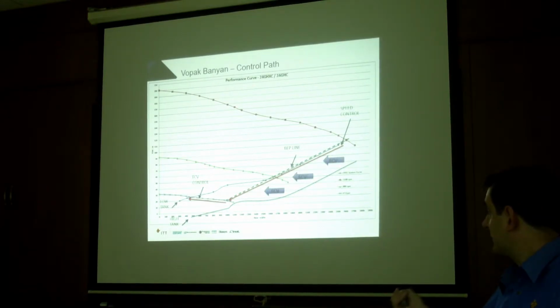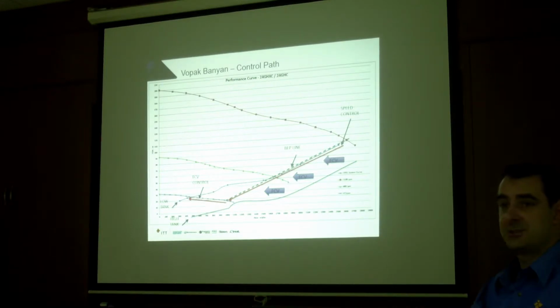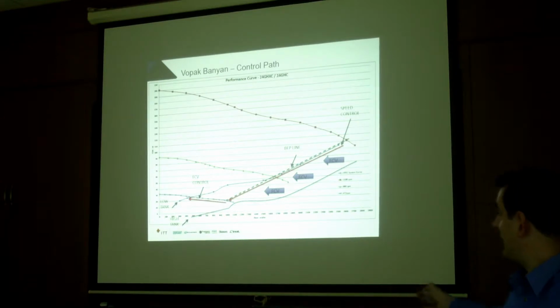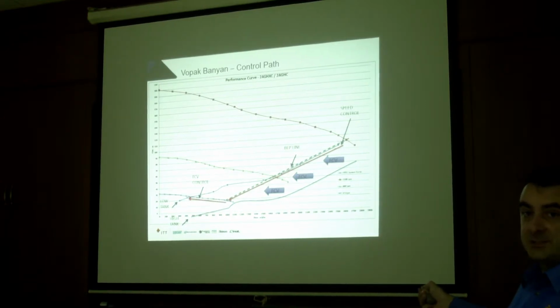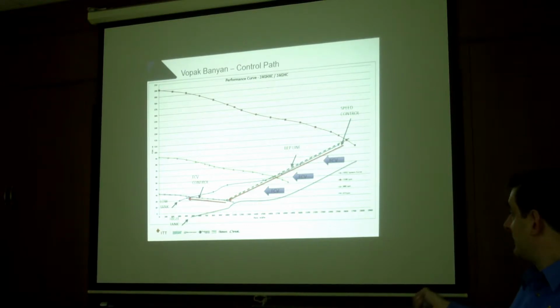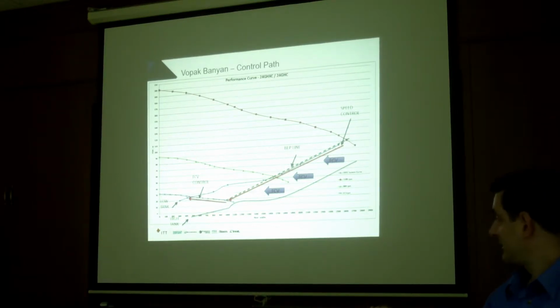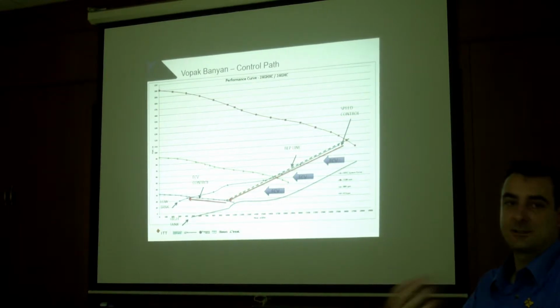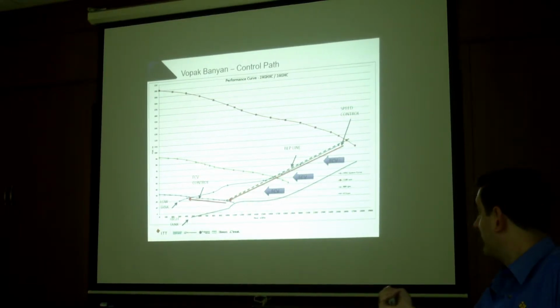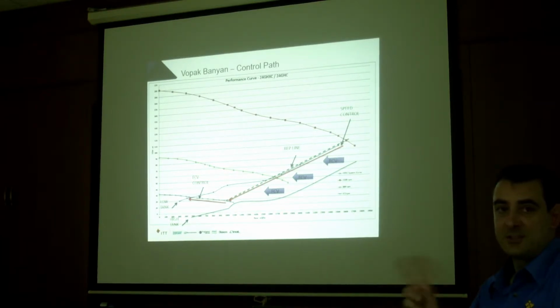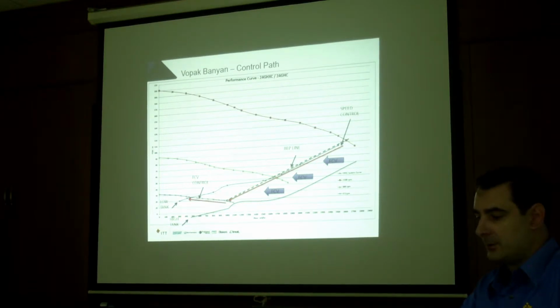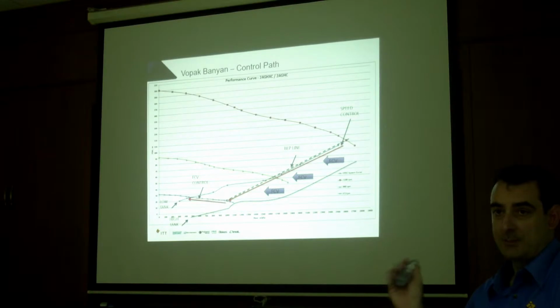At any of these other points, when we're off the end of the curve, we can use the flow control valve to push back and land on the best efficiency point line. So overall, this pump, no matter what the system conditions, no matter what the liquid, will run the best efficiency point to the minimum speed, and then when they still want to go lower flow, we reduce with the flow control valve. So the customer can choose whatever speed, whatever flow they want. They just select flow. And in all cases, they want a high flow until they settle the roof when they want this flow. So they had two choices, but they can choose whatever they want. And that one's the most successful application we have in the region.